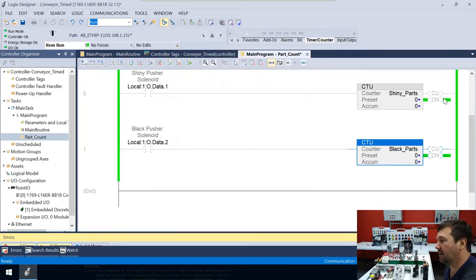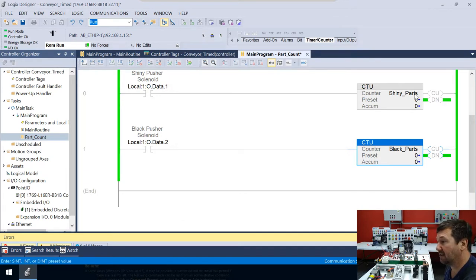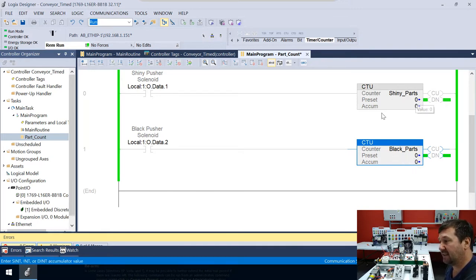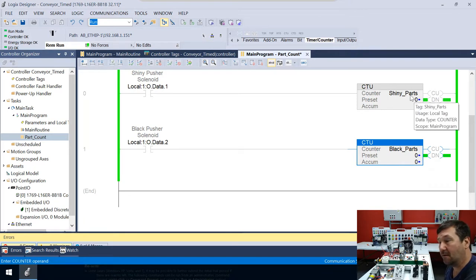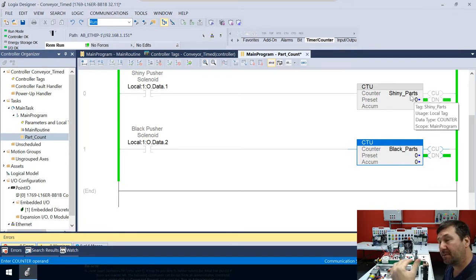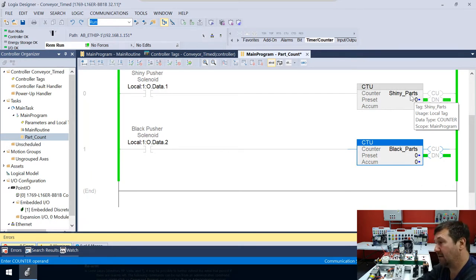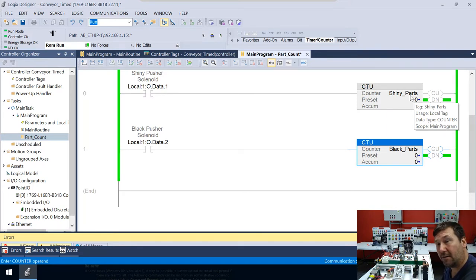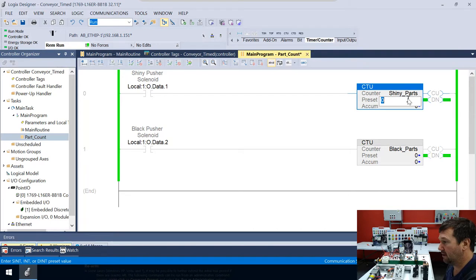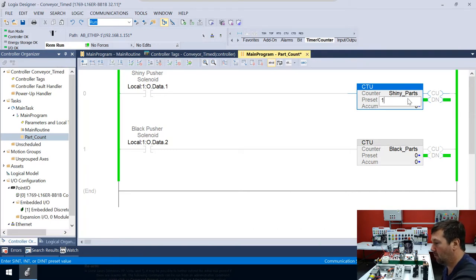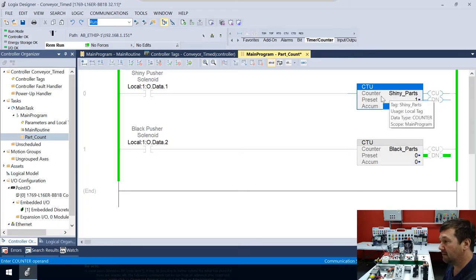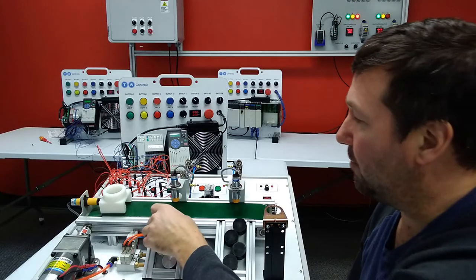So you notice our done bits are already set on these counters. And that's because these counters preset is zero. And the done bit preset on a CTU will be true when the accumulated value is greater than or equal to its preset. Right now it is greater than or equal to it. But if we went here and we just threw a one in, then you'll see the done bit goes off. But really right now, I just want to zero in it because really we just want to count parts. So I'm going to drop a shiny piece in.